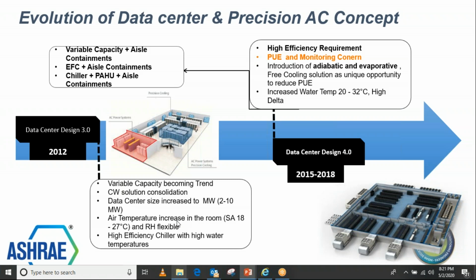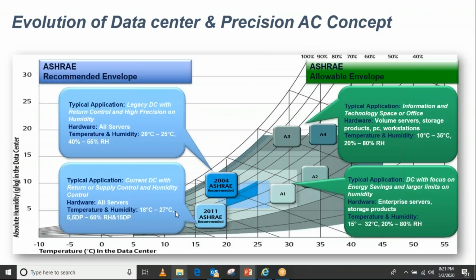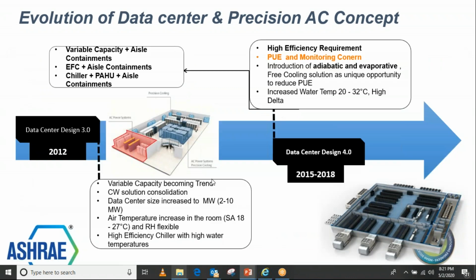Because when you have moved in the previous slide, when you have moved in the envelope from 20/25 to 18/27 in the cold aisle, now imagine across India or many parts of the world where the ambient temperature is low, in your data center you can always have an air to air kind of heat exchanger which will allow the outside air to cool inside data center air and still maintain your data center temperature. So this evaporative kind of air to air or even direct free cooling approach, in some cases where the environment allowed, was actually used to save a lot of energy on the compressor.